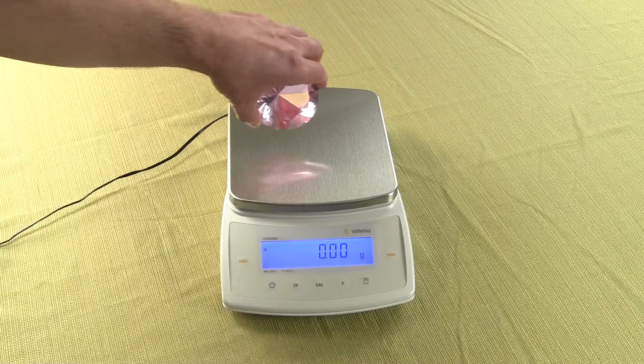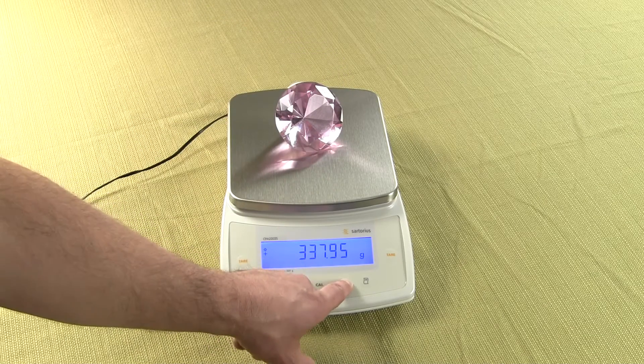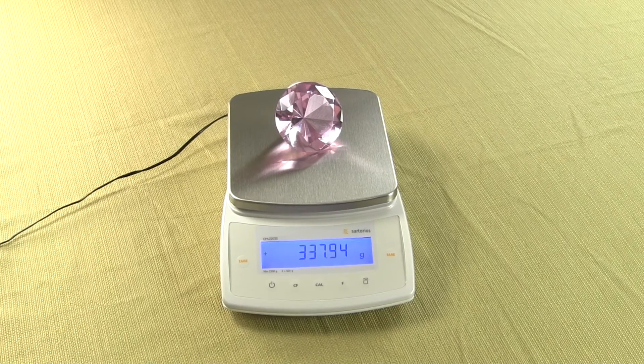The balance powers up in grams. If we hit the F key, we're not going to get a secondary weigh mode because the default doesn't have toggle weigh units enabled. So that's how you change the weigh units. We are Precision Weigh and Balances, an authorized Sartorius dealer. You can visit us at balances.com or scaleman.com. Thanks for watching this video.